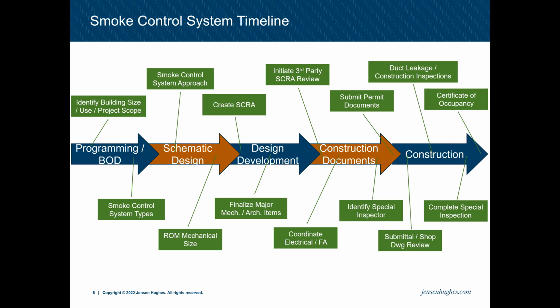And then usually in the end of schematic design, you start to identify a rough order of magnitude for mechanical size. Most smoke control systems are heavily based on mechanical equipment, whether that is supplying air to pressurize a stair or an elevator, or exhausting a lot of air in an atrium to maintain tenability in that space. In the schematic design phase, you start to get an idea of what size fans you have, so you have an idea of where those can be located, kind of pricing for those, power draw for those, etc.